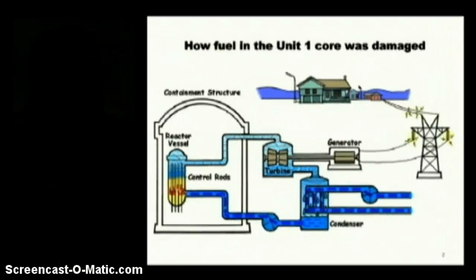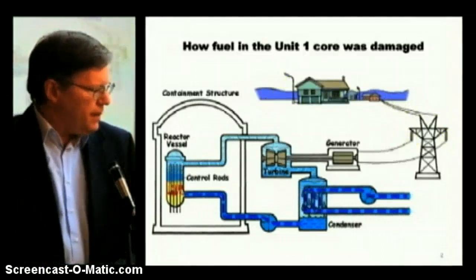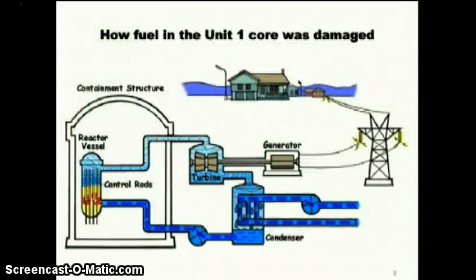There were six reactors at Fukushima. Three of them were operating at the time; three were shut down for scheduled refueling. In a boiling water reactor, the nuclear fuel is inside a reactor vessel. The heat from splitting atoms is used to warm water flowing upward through the reactor core, causing it to boil. The steam leaves the reactor vessel and is carried through piping to a turbine connected to a generator. The spinning turbine generates electricity. The steam leaving the turbine is passed into a condenser where seawater cools it back into water, which is then sent back to the reactor and reused.